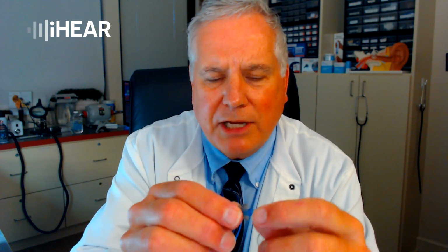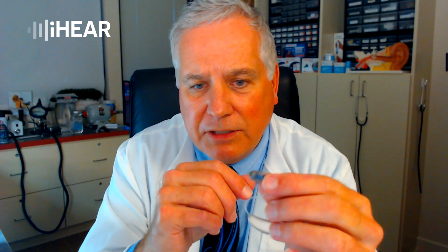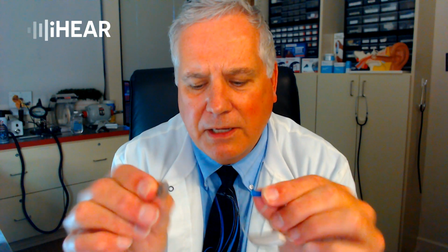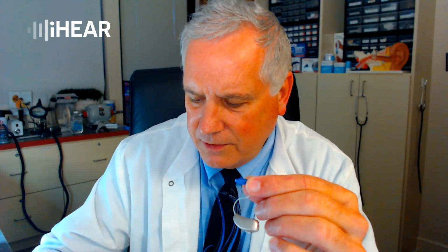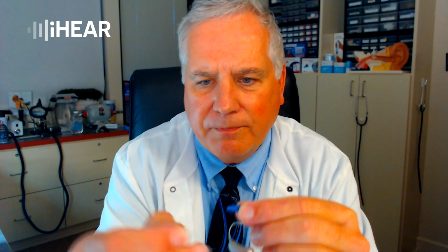But so you may need to change the domes, and also you may need to change them from time to time for cleaning purposes. And when they get worn out, you'll want to change them. And they're very easy to do. You just grasp it at the tip, just pull it off, twist it a little bit, and it comes right off. Okay, I'm going to get another dome here. I'm going to select an open dome, and I'm going to push that onto the end of the receiver and push it down, twist it a little bit, just make sure it's secure. And there I've changed the dome from a closed dome to an open dome.